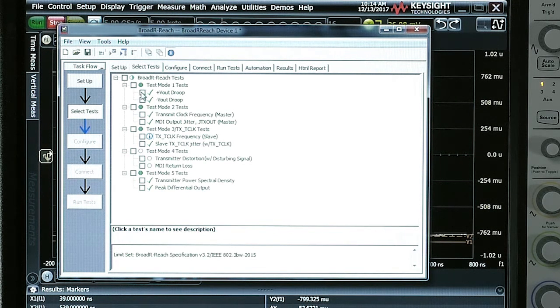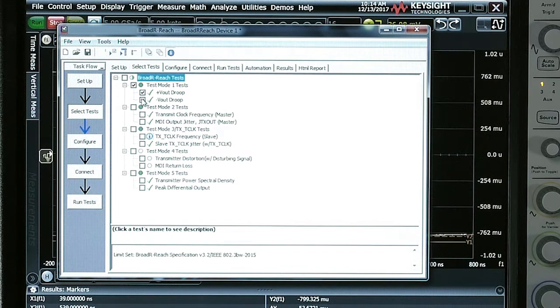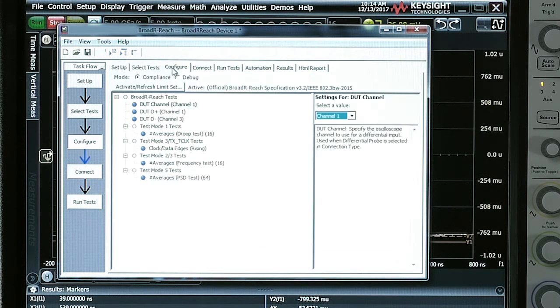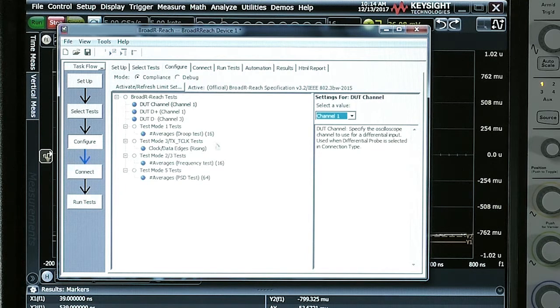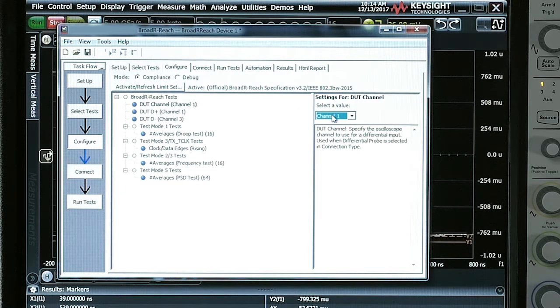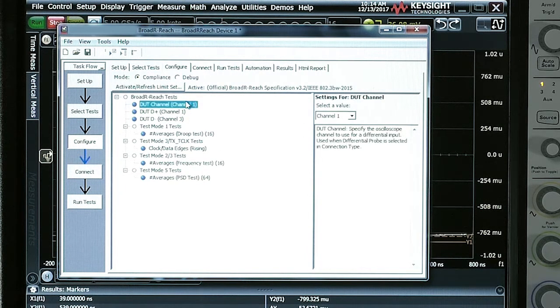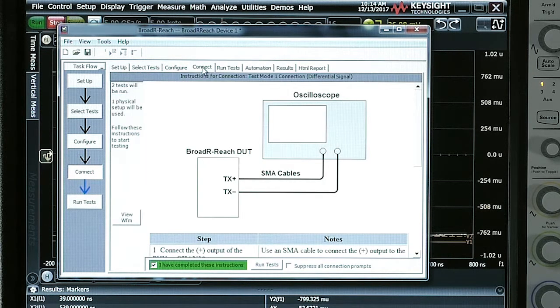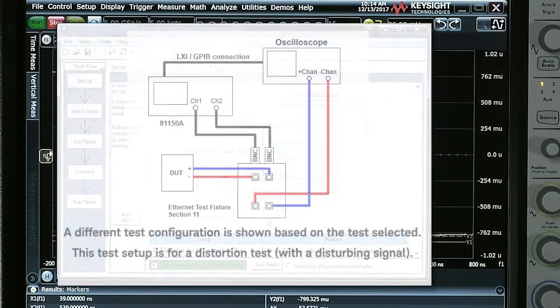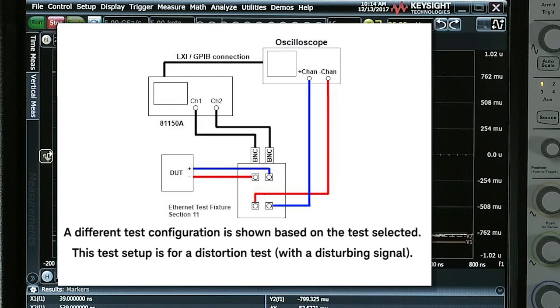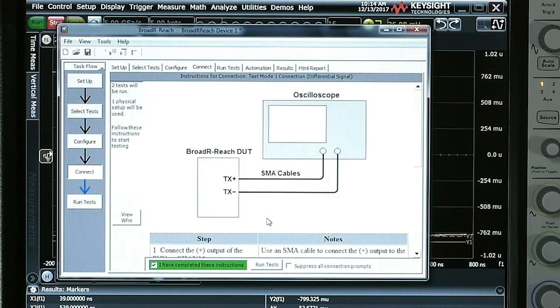I'm going to choose a couple of these tests and we're going to walk through these tabs to see how the compliance application works. Under the Configure tab, I would select which channel my DUT is connected to. Under the Connection tab, you can actually see the oscilloscope connections with the SMA cables to the device under test and that's for each specific test that's being run.